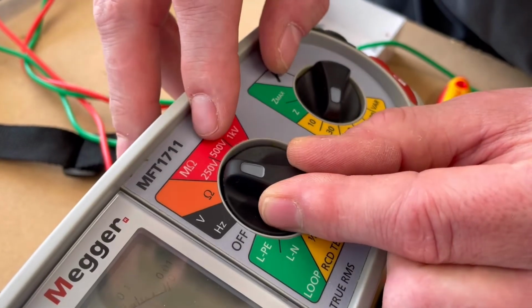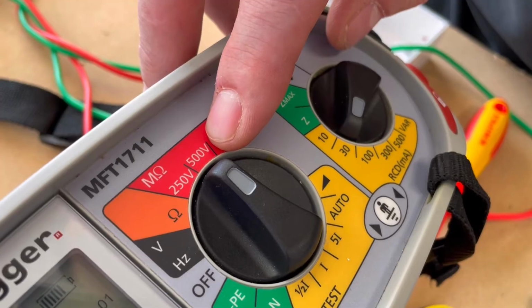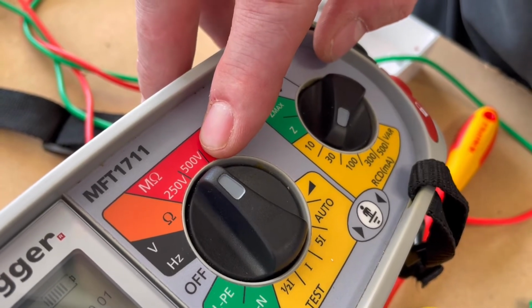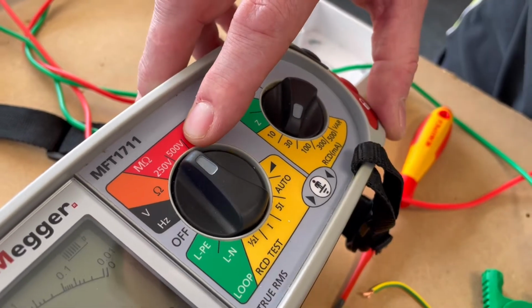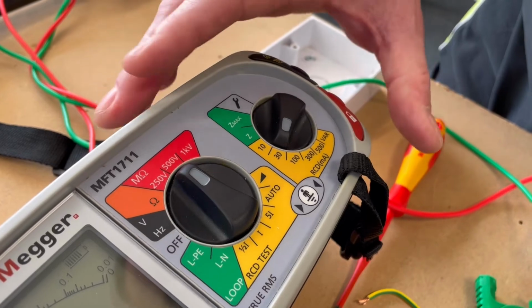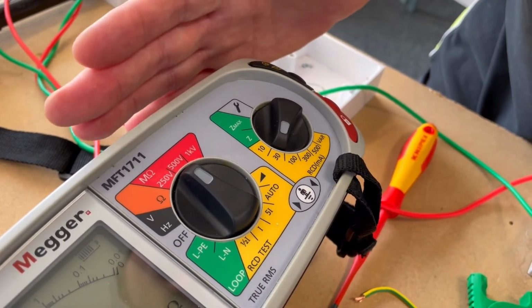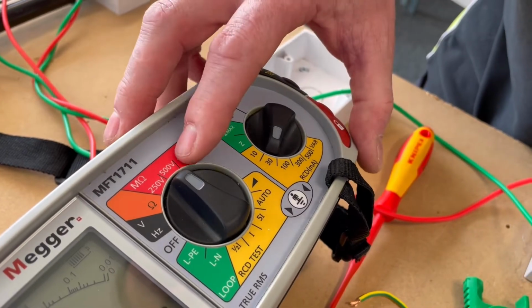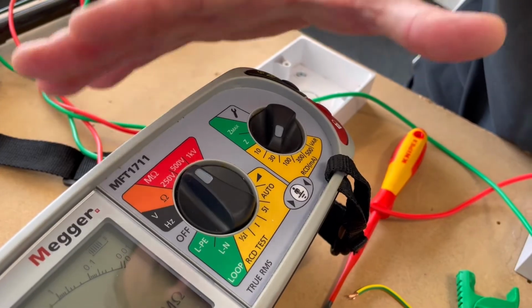And now there's 3 voltages to choose from. For our system, we're going to test it at 500 volts DC. And the On-Site Guide says that we should achieve a minimum insulation resistance of 1 megohm. However, further investigation at 2 megohm. But if you look in Guidance Note 3, it says for a brand new installation, it shouldn't be less than 20 megohm. Okay, so we've got a brand new installation. I expect the insulation resistance reading to be very, very high.